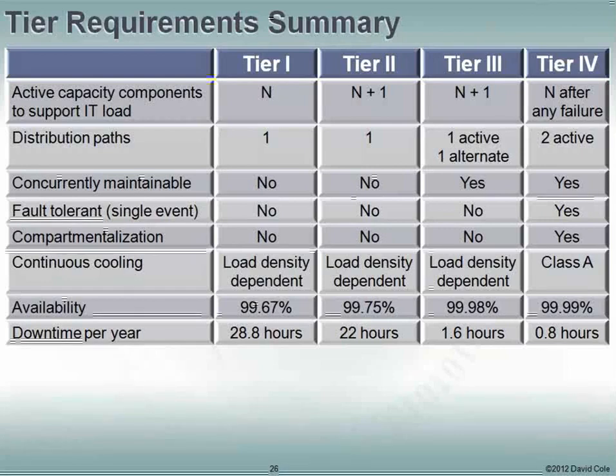I'm now fault tolerant when I get to Tier 4. I've compartmentalized, meaning everything stands on its own at Tier 4. Continuous cooling is also introduced in Tier 4. Class A cooling just means the cooling will be on regardless of the power situation.